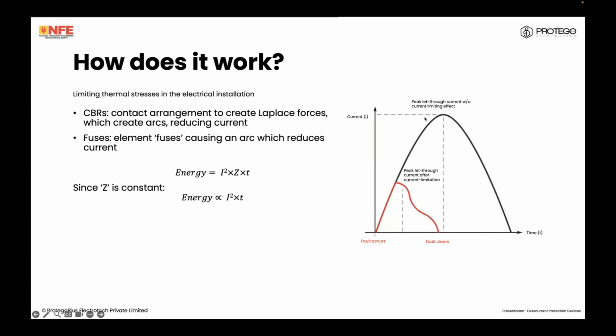So if you look at this black line, this is the peak let through current without the current limiting effect. And the red line is the peak let through current after the current limiting effect, once the fault clears. So the amount of thermal stress, the amount of energy seen by the wiring system, is greatly reduced. Therefore, this will greatly affect the cable sizing calculations and the amount of stress the system is put under.